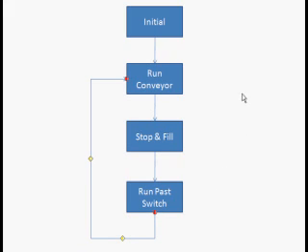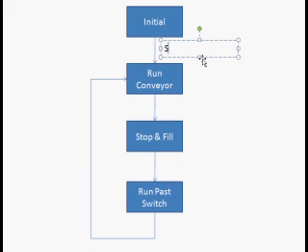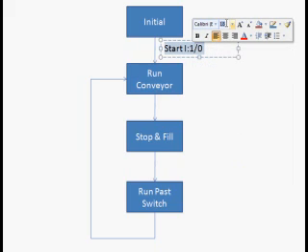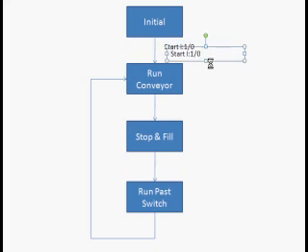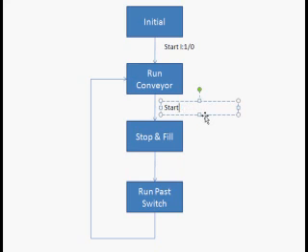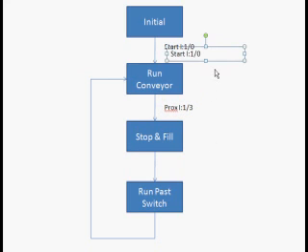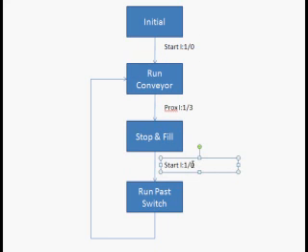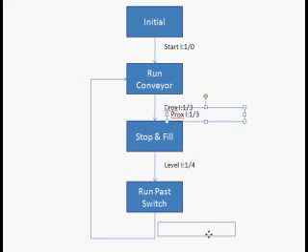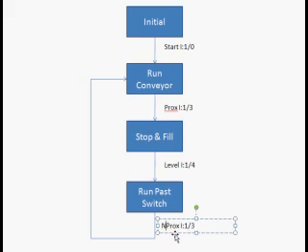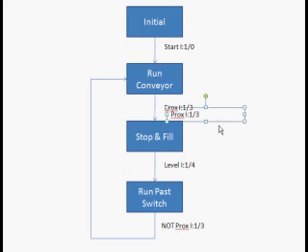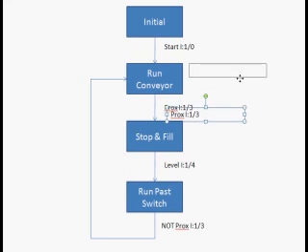What I'm going to do now is put a label next to every arrow showing the conditions that it takes to move from one step to the next. We're going to call these our transition conditions. After initial we're going to use the start button so once the start button is pressed that's what's going to move us down to the run conveyor step. After run conveyor we want to stop and fill after the Prox switch is made and when we're stopped and filled we make the level switch and that will move us down to the next step which is run past the switch. After run past switch we're going to put NOT Prox and that means when the Prox switch is no longer made. Once it's no longer made it means the box has passed it and we now want to loop back up to the run conveyor step to where we start all over.